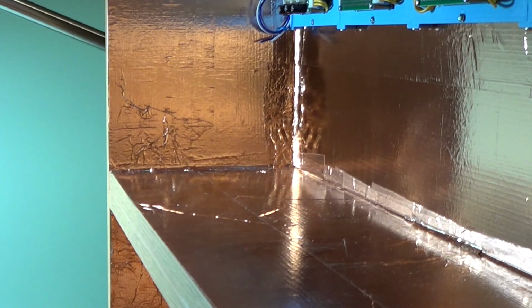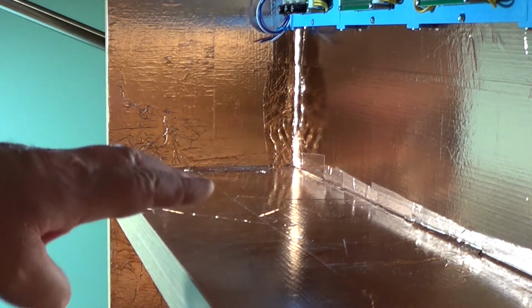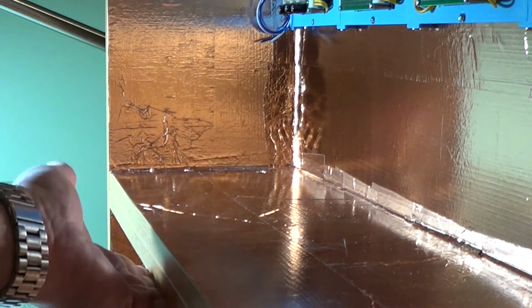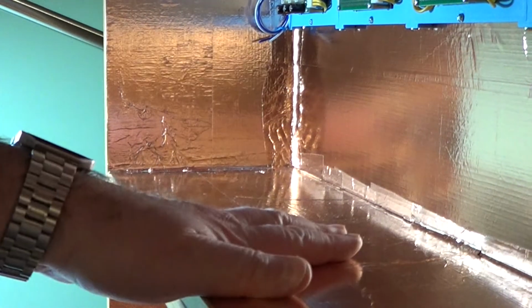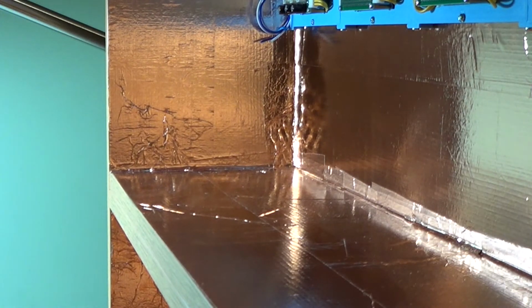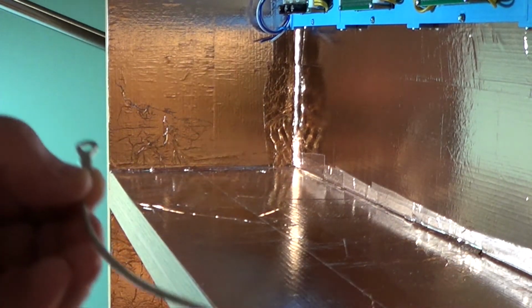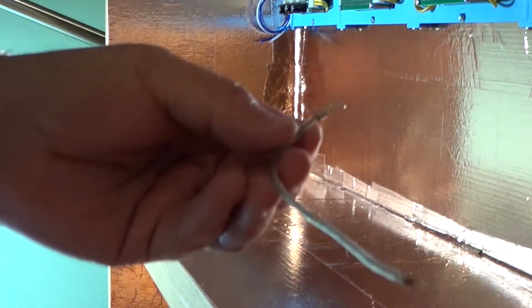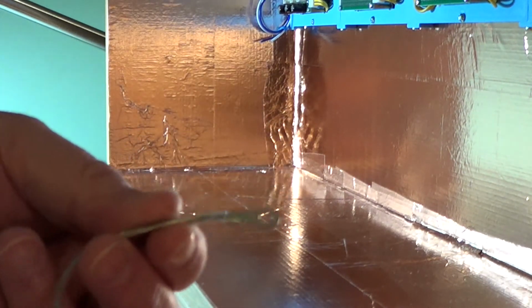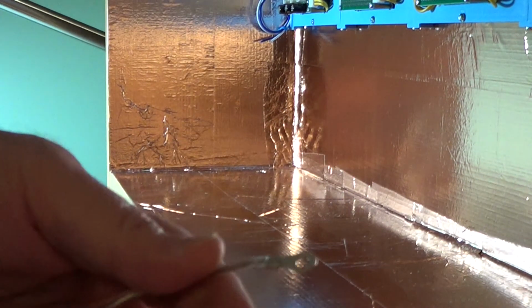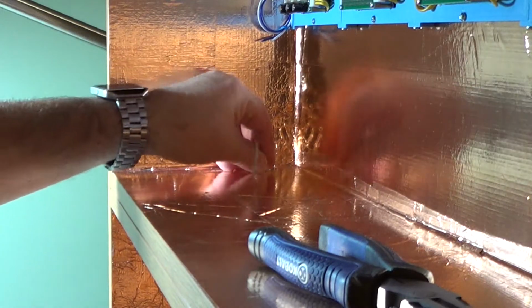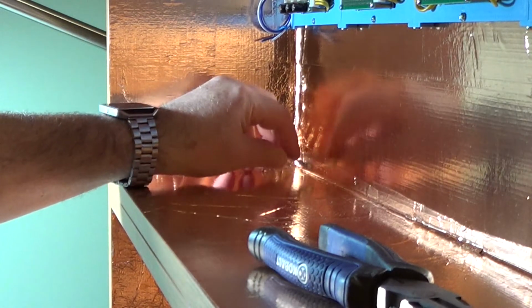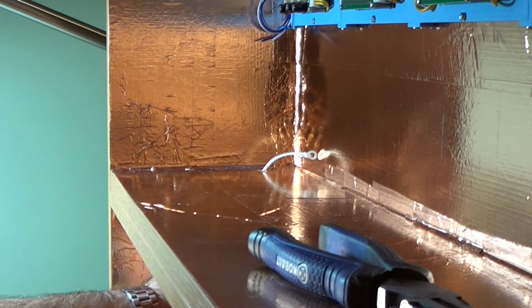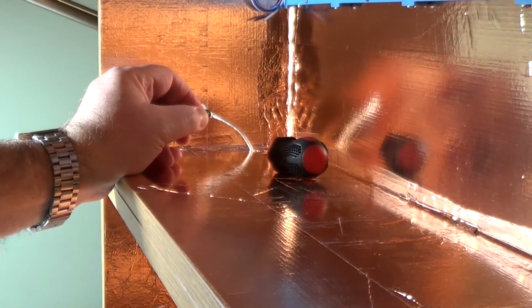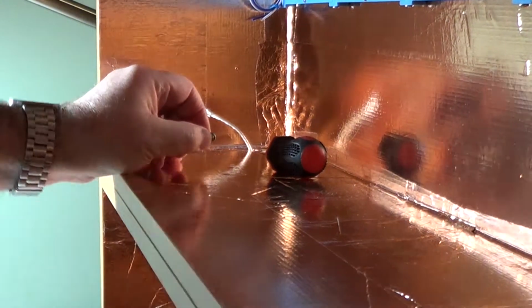Let's now start the assembly of the modules on the shelves of the rack. The first thing we need to do is electrically connect the upper shelf and lower shelf shieldings. For that, I'm going to use a wire I already prepared with connectors at both ends that can be screwed directly to the walls of the shelves. I'll fit the wire through the hole I prepared when assembling the rack itself. Now each end of the cable can be screwed onto the wall on each shelf.